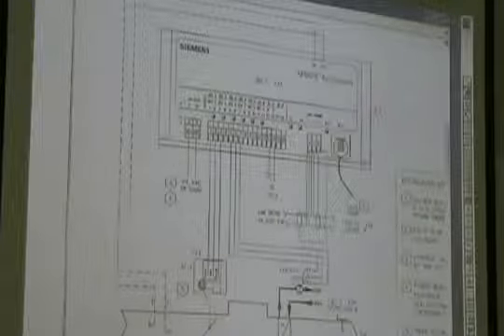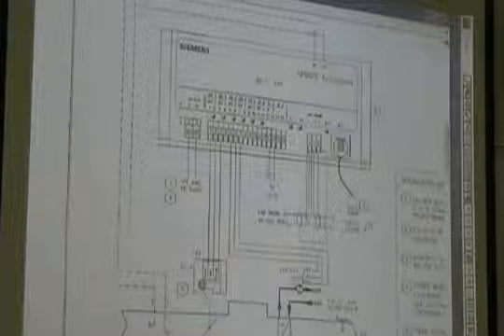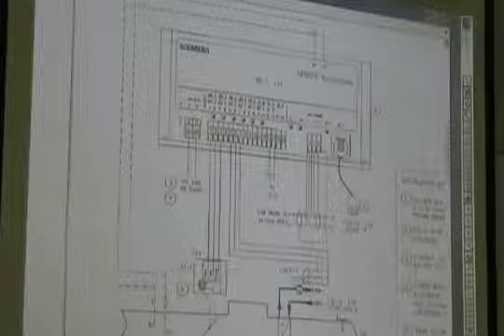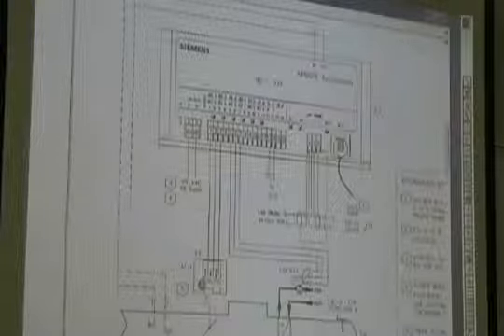Thomas, is there anything special about that cross flow sensor? I mean, if the one in the VAV is messed up, can you just add another one later? You can buy aftermarket ones and put in there. Does it work just the same? They work, they all do the same thing, but airflow velocity pressures are extremely low. And if you've done much pressure measuring, you know that measuring extremely low pressures is difficult. So what almost all of these probes will do is amplify that velocity pressure signal. So the only difference between one pickup to the other, some of them amplify it differently.